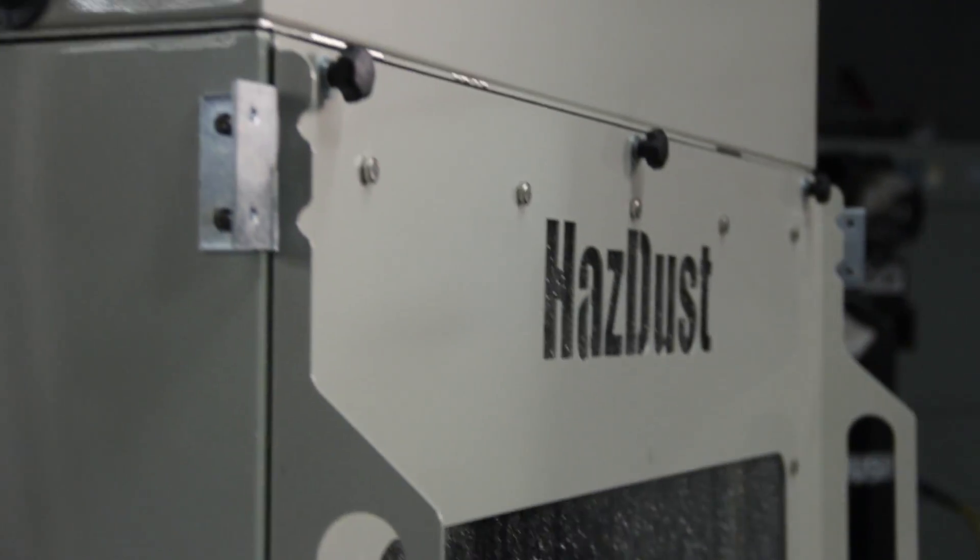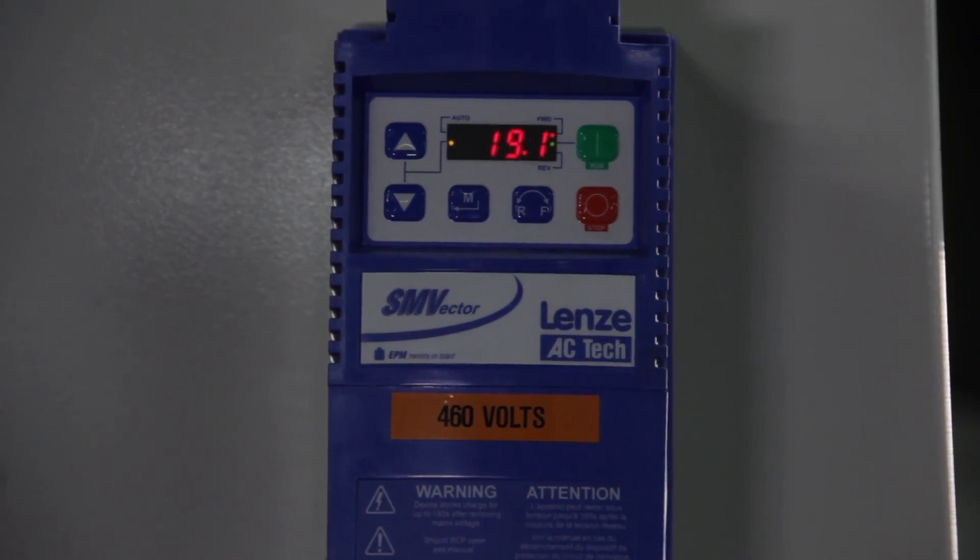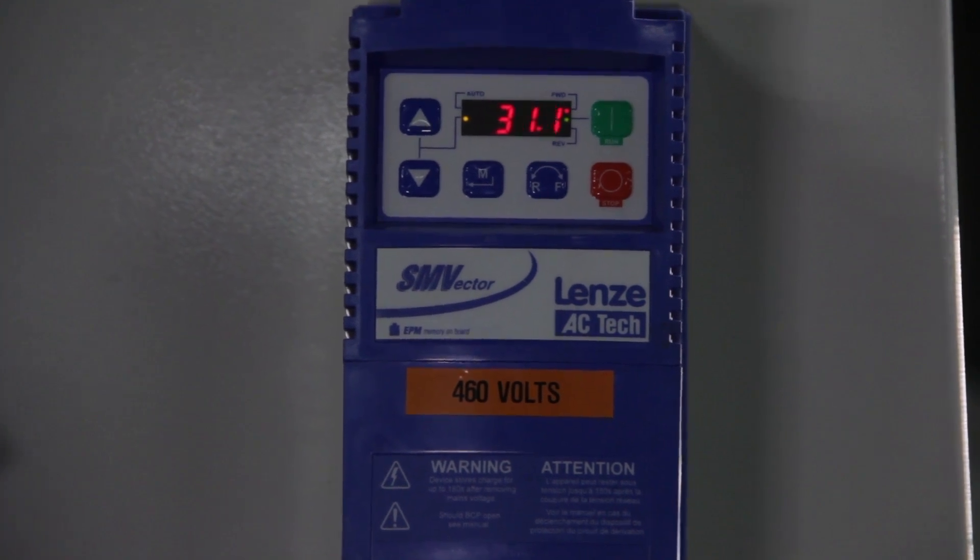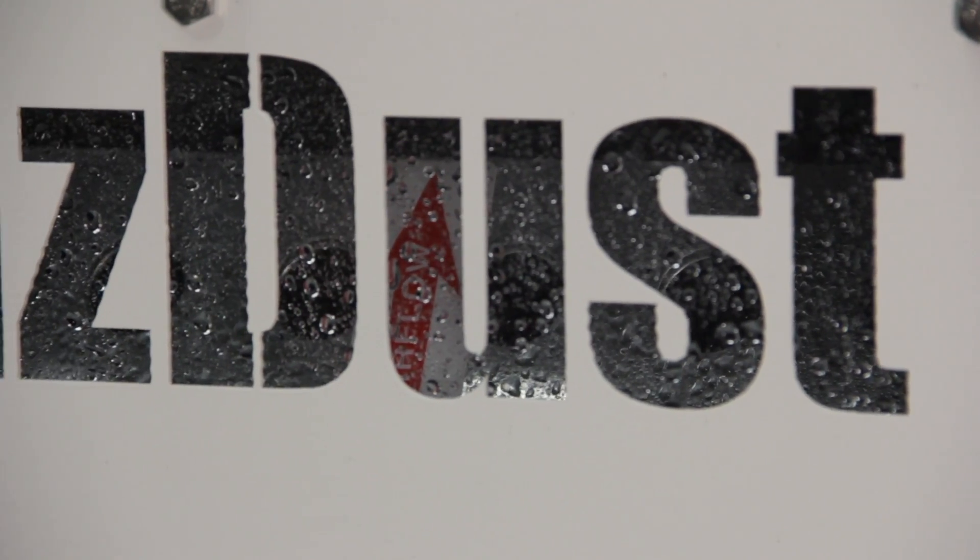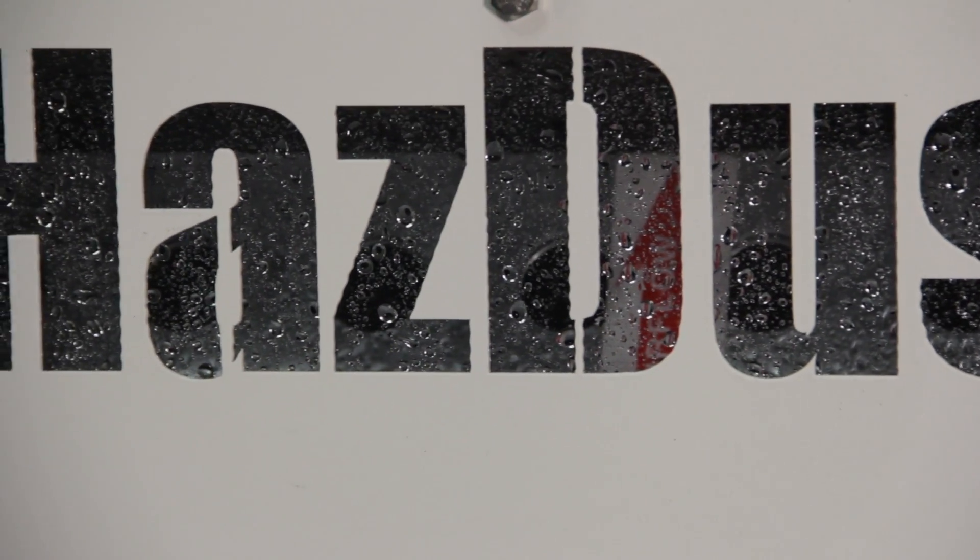Control panel houses a motor starter and relays that control the water solenoid and is tied to conductive water level probes. Four probes total: two control the operating level of the water, one is a high water level shutoff shutting down the motor if the water is too high, and a low water shutoff shutting down the motor if the water level is too low.